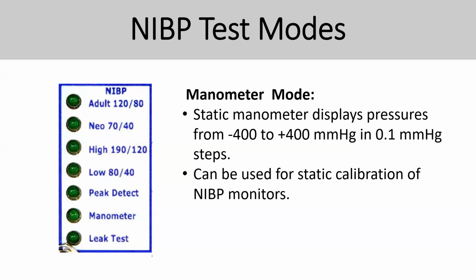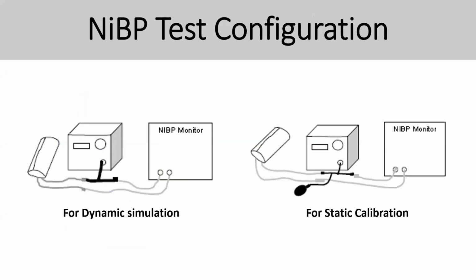So NIBP test mode, these are basically what you're going to see on the SimCube unit. You're going to see adult, neonate, high, low, all these are basically NIBP simulation, and you've got manometer, leak test, all this. NIBP simulation configuration: when you talk about dynamic simulation, you're going to simulate a patient condition on the patient monitor. For static, basically you're going to calibrate the pressure, or sometimes do a leakage test. You need to use this particular configuration.